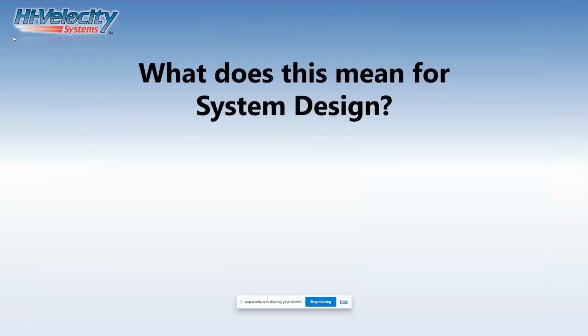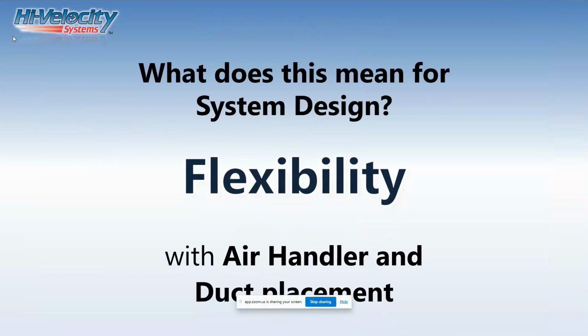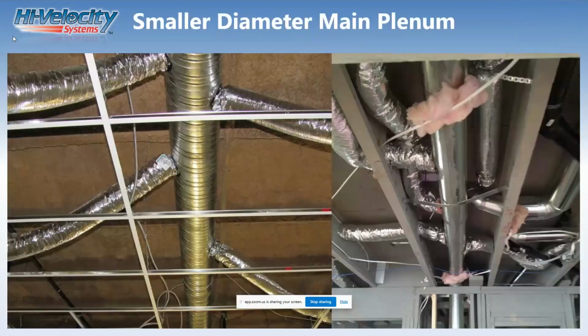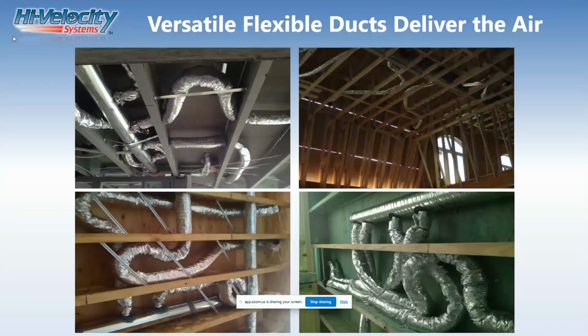Again, what does this mean for system design? Flexibility in air handler and duct placement. Well, again, we're using small ductwork. We can fit one plenum in the joist space and now take off a flex and go to each individual room to dissipate that air, instead of running 5-inch or 6-inch pipes, and we're looking for a lot of wall space to bring them up. Again, smaller ductwork. Another application of flexible ductwork, we can go in the ceiling, the joist space underneath.